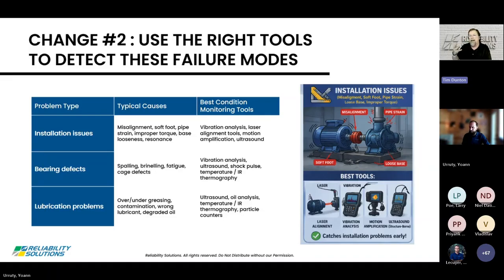When we look at a rolling element bearing, a ball bearing, there are three types of friction present. One is rolling. Another is sliding, as the balls or rollers slide by the cage. And the third is fluid friction. Of those three, fluid friction is by far the biggest source of friction. A byproduct of friction is heat. Heat reduces oil film thickness, and on and on and on, right?